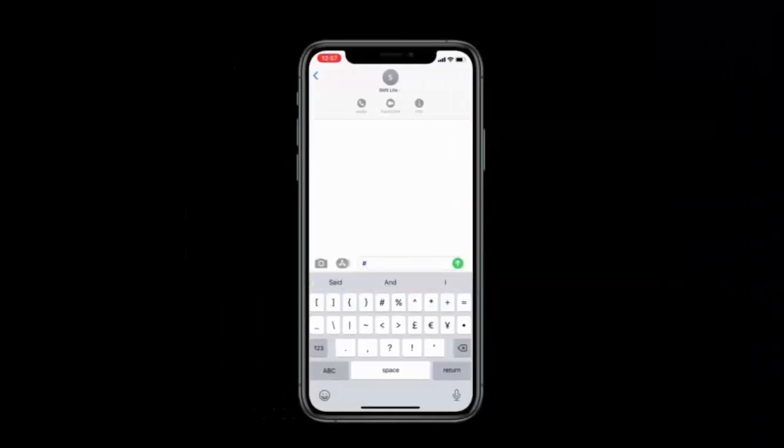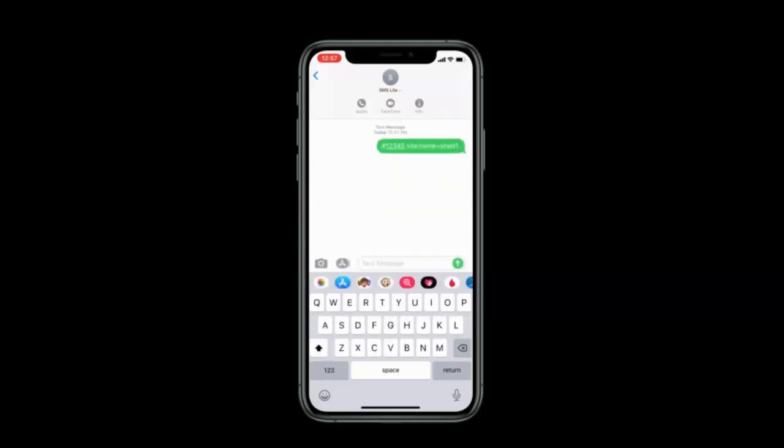To set the name of the site where the SMS Lite is installed, we send a command to the device starting with the hashtag and then the PIN number, which is located inside the device's case. We follow this with a space. For this example, the object we're referring to is site, and since we want to configure the name of the site, we write site:name. You then place an equal sign, followed by whatever you'd like to rename the site, e.g. Shed1. Don't forget to end your text with a full stop, otherwise the SMS Lite will not recognise the command.